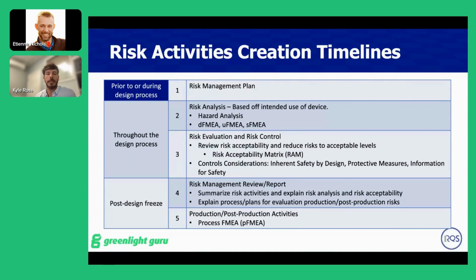ISO 14971 standard specifically calls out the use of a hazard analysis and a risk analysis method that is aligned with the standard to cover potential harms to the user or the people that are administering the device or test, and anything that could go wrong as far as user harm. That is the key requirement from the standards to have this hazard analysis. In some cases, depending on the device and complexity of the device, you might need to also supplement with other types of risk analysis. FMEA is a very common one for this type of risk analysis. Fault tree analysis and other tools can also be used to align with the standard and provide additional risk analysis at different phases. We'll cover that later in this section on when to implement FMEA and when a hazard analysis might be enough for your type of device.